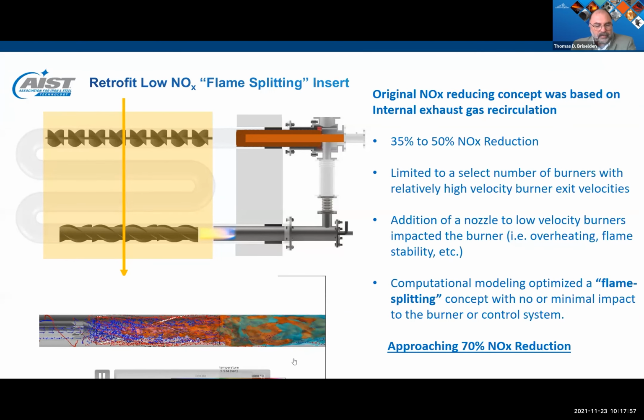Due to the impact on the burner and control system, a computational evaluation along with laboratory validation identified an effective means of NOx reduction with minimal impact on the burner or control system. Flame splitting is showing the ability to reduce NOx by up to 70% in a variety of existing burners. This includes nozzle mix, partial premix, air or gas stage combustion, and low NOx burners with and without exhaust gas recirculation.